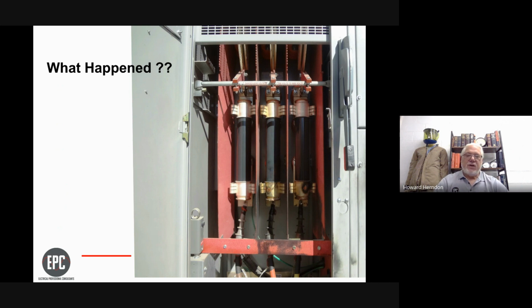The gentleman's job for the day was that they had just gotten onto their one-year mark, when they were going to fully turn the job over to the state, and they could then collect their retention. Their job was to make sure that the system was properly working. That's typically done by a couple of measurements. The first one was to do an infrared scan of all the connection points within the electrical system. The second way was to measure both the DC output of the PV panels and then look at the combiner boxes as a group and see what they were actually outputting to the inverter. And then the inverter converts DC power to AC power so we can use it in our normal electrical systems.